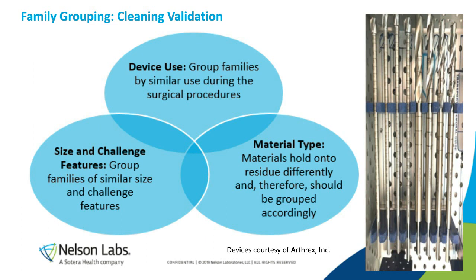This is a really interesting part of grouping devices. There are different ways to group devices, and first I'll go over how to group devices for cleaning validations. To do that, we look at three aspects of these devices. We first want to look at the device use. Devices can be grouped by their function, use, and degree of patient contact based on intended use. Similarly configured devices or parts used for generally the same purpose and that contact comparable amounts of human tissue, blood, mucus, etc. may be grouped together for a validation. We then look at the material type, since materials range from metal to ceramic to polymers, usually a mix of several materials located on different devices, and materials hold onto residue differently and therefore should be grouped accordingly.